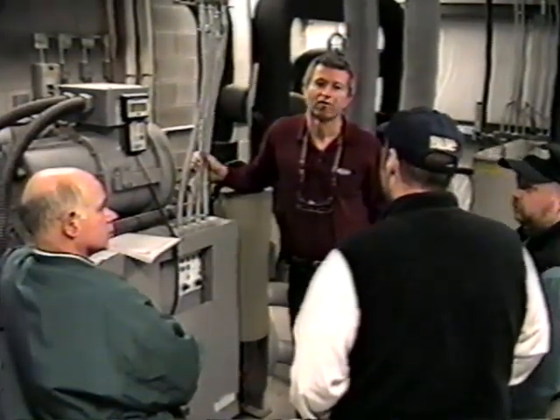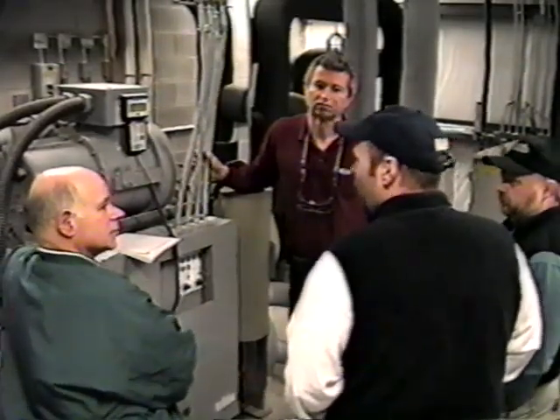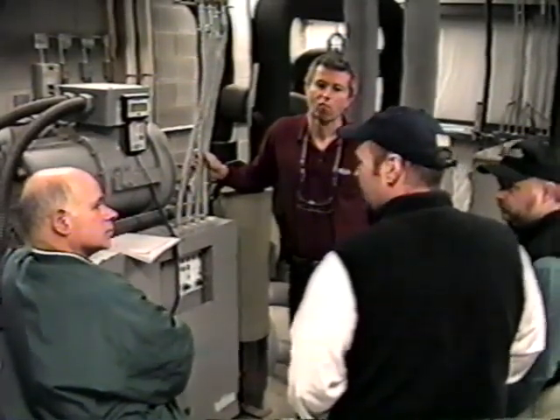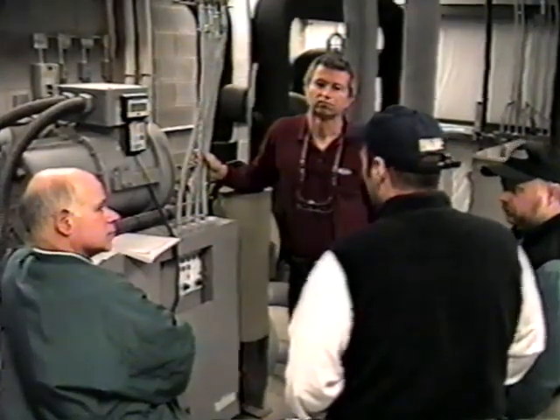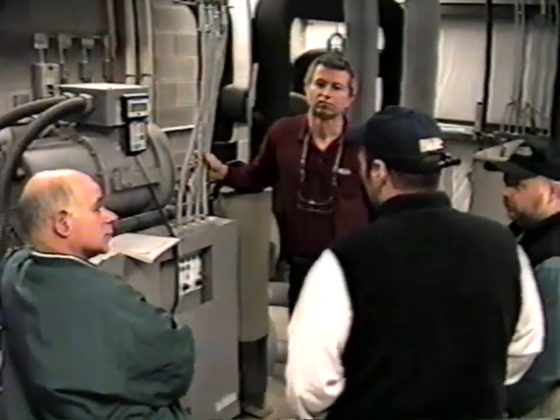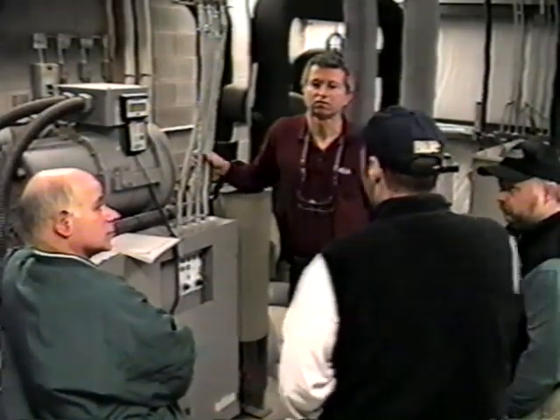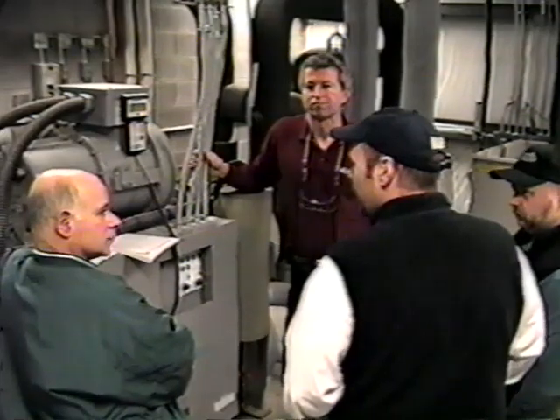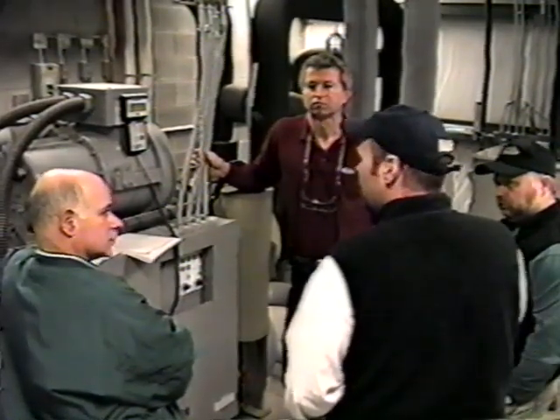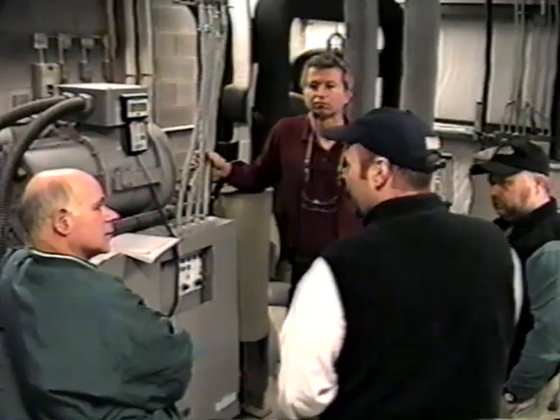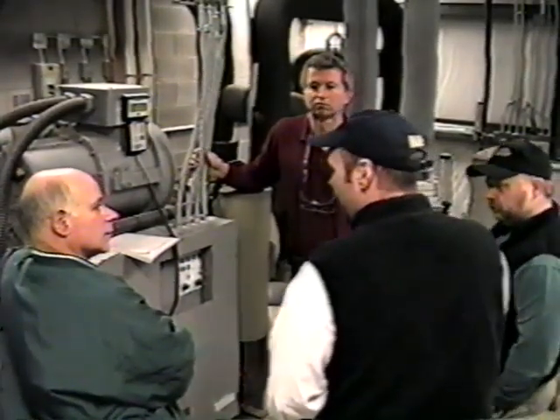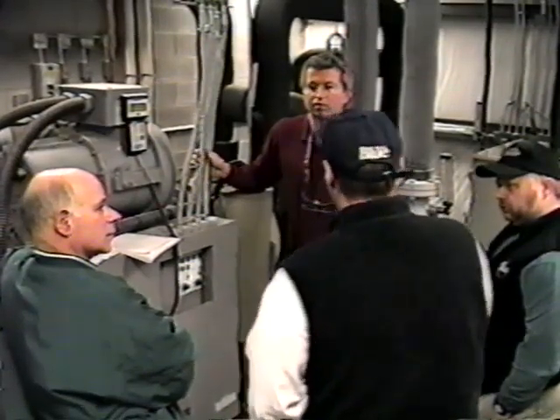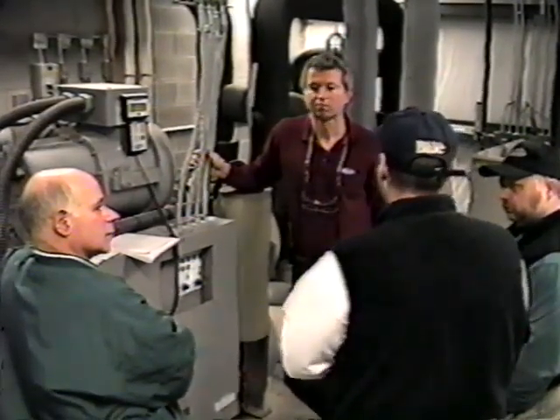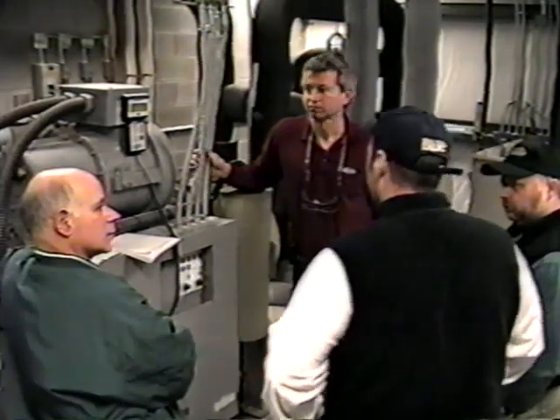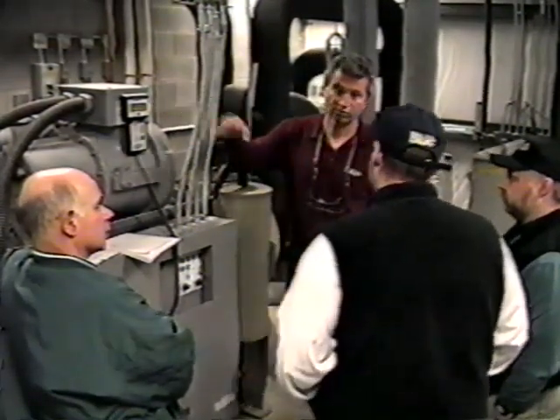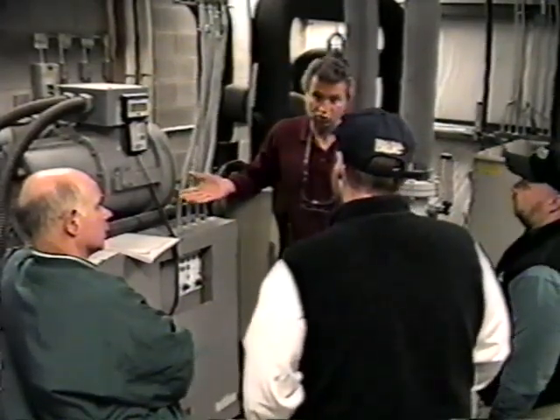Yeah. Well, over there, I've got it set at like 17 or 18, depending on what it is, and then I'll just raise it up to like 24. Yeah, and then those compressors, nothing will be running all day. We're not using it all day, there's no heat load or anything, the lights aren't on, so I'll want them off. It'll raise the temperature, then before college practice starts at 3:30, usually by 3 o'clock, I'll turn it back down. It's a half an hour to start drawing it back down, and that helps bond the ice, makes it a little harder with this kind of system. Yeah, essentially, it's probably going to work by just doing that, because at that point, it's going to shut the machine off.